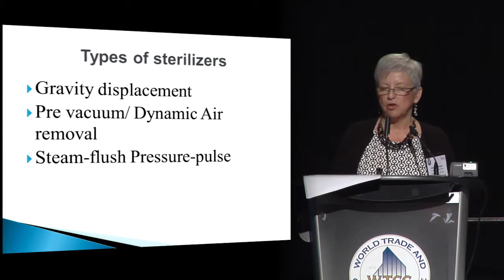Dynamic air removal sterilizers, or pre-vacuum sterilizers, remove the air from the chamber with the use of a vacuum. This method is much more effective in removing the air from all the packages. This type of sterilizer does require additional monitoring. It would require a Class 2 chemical indicator, and this indicator is basically just an air removal test. It just shows that the air has been taken out of the chamber. And I'll show you what that looks like and how you would interpret that test.